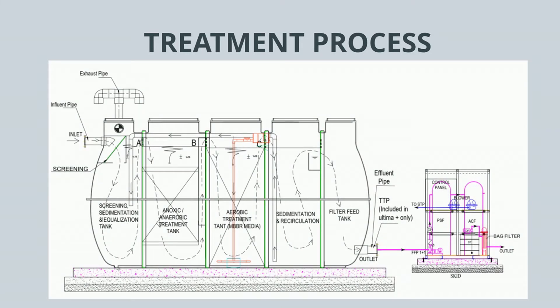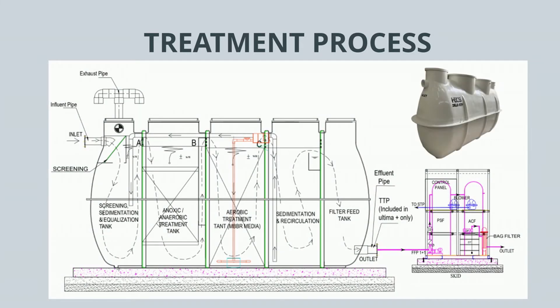Our compact STPs have a proven treatment process sufficient to meet the Indian standards laid down by MoEF&CC. The treatment process consists of a screening chamber for separating solids and plastics present in the sewage, followed by an equalization and sedimentation tank, an anoxic treatment tank, an aerobic treatment tank, and an activated sludge sedimentation tank with a recirculation system.